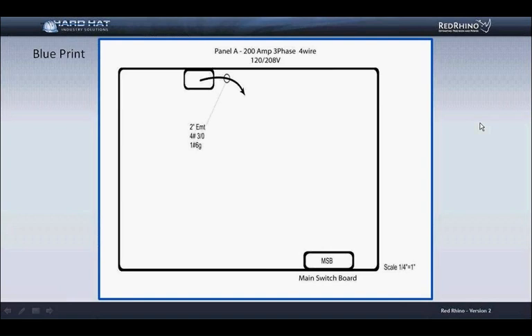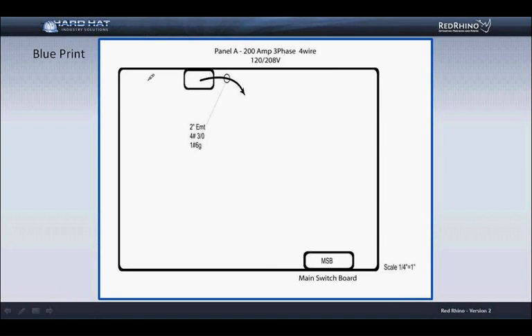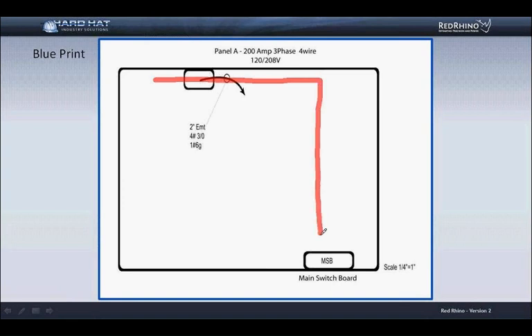For those who may not know what the definition of a conduit riser is, this refers to the conduit that runs vertically. An example of the conduit running out of the top or bottom of a panel or junction box. Here's another tip. You can allow for the riser conduit by overrolling or rolling past the end of the conduit run. When you roll past, it adds extra length on the Scalex.